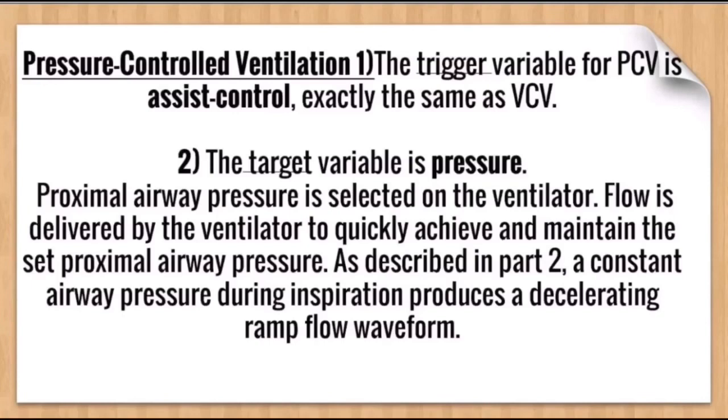And when the flow is delivered quickly, there is a naturally produced decelerating waveform pattern. So in pressure control ventilation, we will have the flow wave, that is the decelerating waveform pattern.